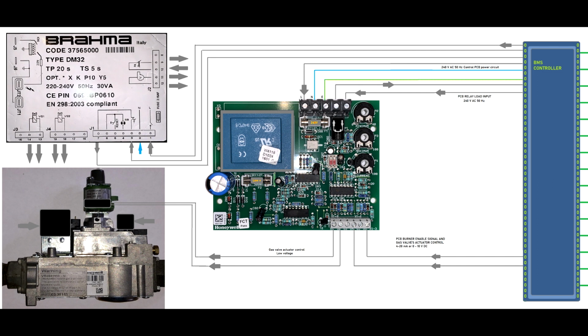Now this Brahma controller, it's also connected to this building management control, and I found on a lot of occasions this type of wiring, you don't have necessarily to connect this Brahma controller to the programmable logic control. This can be enabled directly from this printed circuit board. If you see that relay I was talking to you earlier, when the PLC or building management control BMS send 0 to 10 volts and enable that relay, it can bring power straight into this Brahma directly.